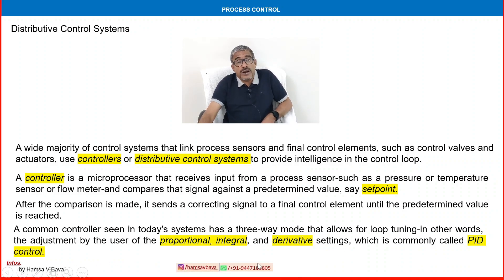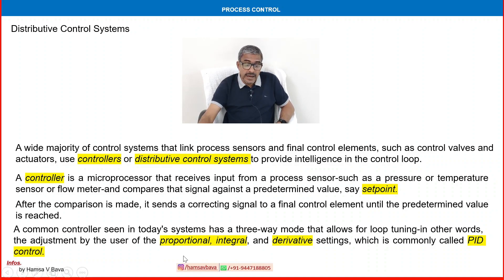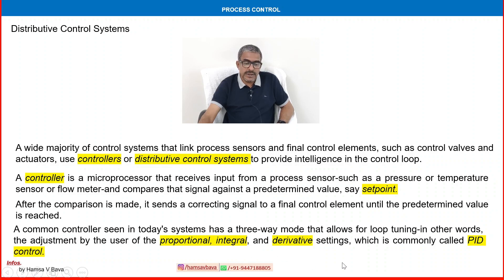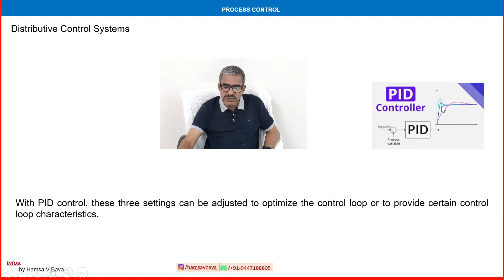A common controller seen in today's systems has a three-mode capability that allows for loop tuning — in other words, the adjustment by the user of the proportional, integral, and derivative settings, mainly called PID. Earlier, control valves used either proportional, integral, or derivative alone, but now advanced PID controllers are combining all three. With PID control, these three settings can be adjusted to optimize the control loop or to provide certain control loop characteristics.